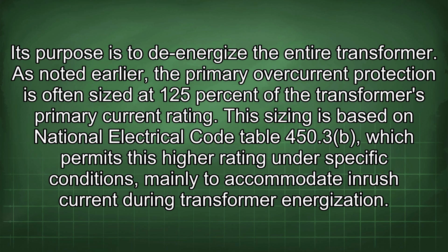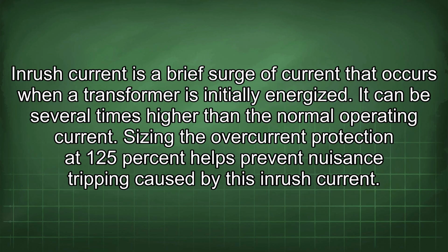As noted earlier, the primary overcurrent protection is often sized at 125% of the transformer's primary current rating. This sizing is based on National Electrical Code Table 450.3, which permits this higher rating under specific conditions, mainly to accommodate inrush current during transformer energization. Inrush current is a brief surge of current that occurs when a transformer is initially energized. It can be several times higher than the normal operating current. Sizing the overcurrent protection at 125% helps prevent nuisance tripping caused by this inrush current.